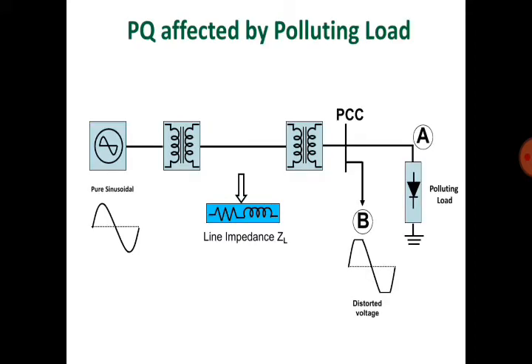Power quality is affected by polluting loads. A polluting load means a non-linear load — any power electronics converter is a type of polluting load because it injects harmonics into the system. The diode symbol in the load indicates a rectifier or power electronics converter. The input waveform is pure sinusoidal, but the output waveform is distorted — this is the effect of a polluting load.